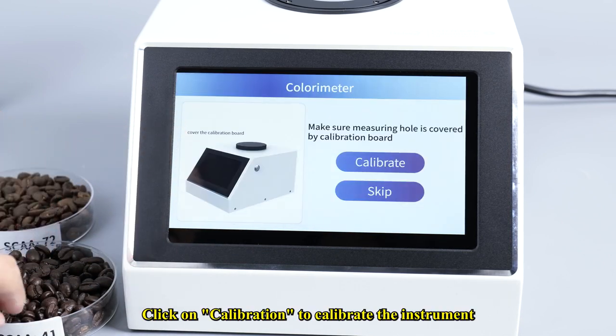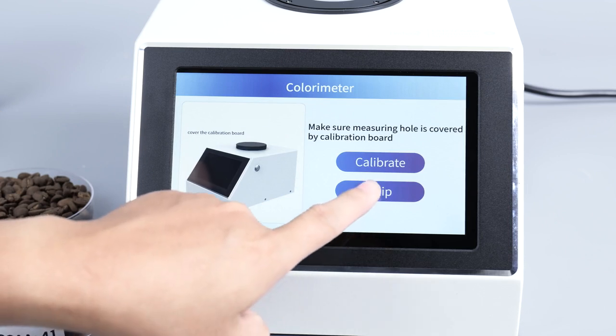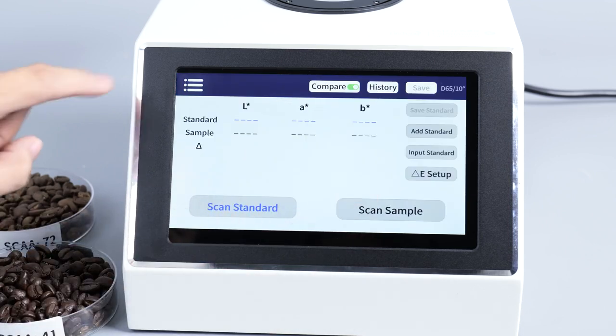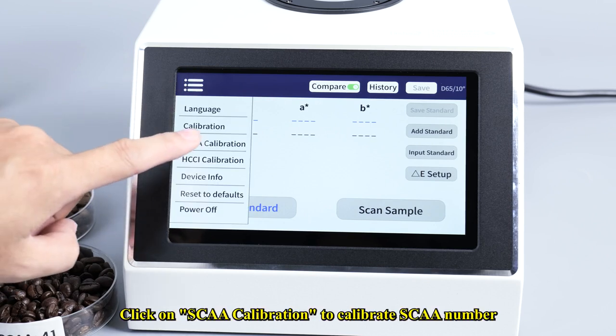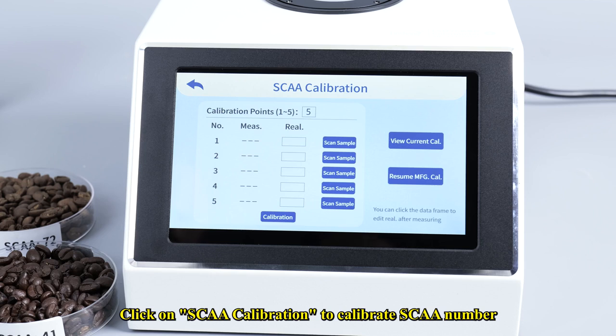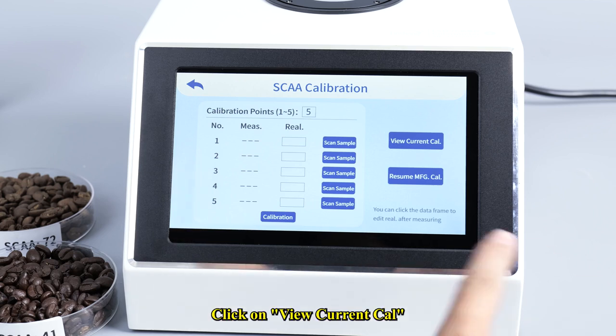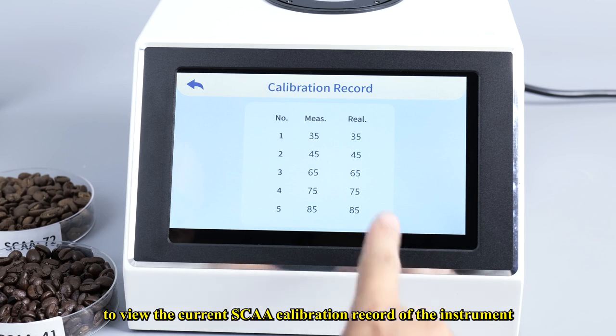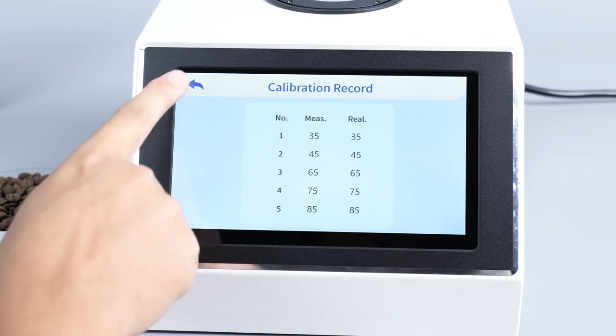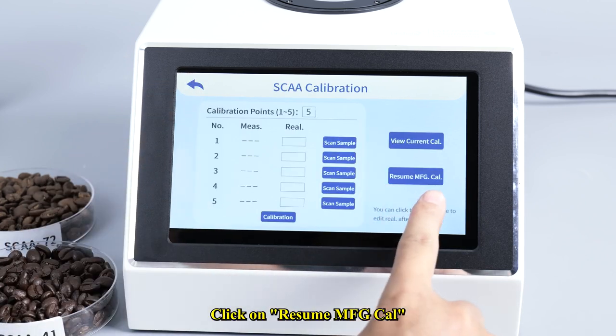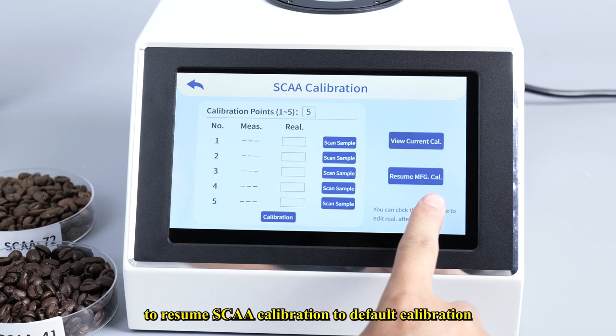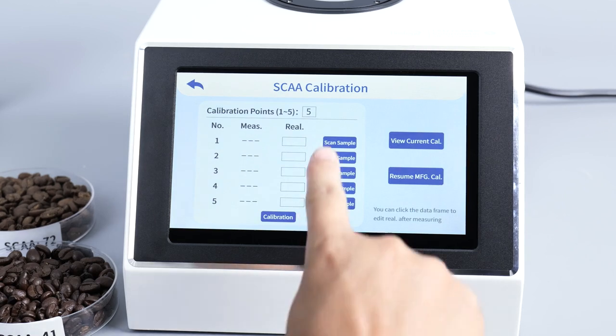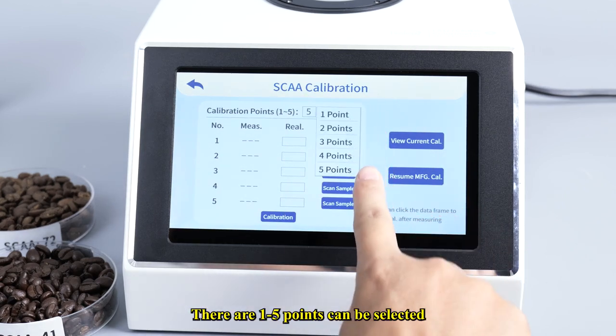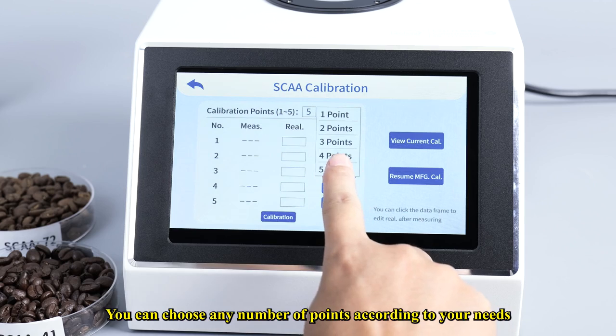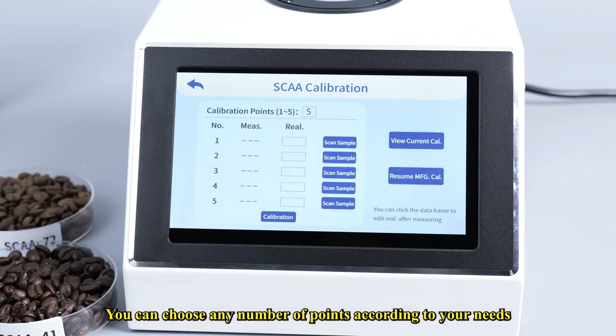Click on Calibration to calibrate the instrument. Click on SCAA Calibration to calibrate the SCAA number. Click on View Current Cal to view the current SCAA calibration record of the instrument. Click on Resume MFG Cal to resume SCAA calibration to the default calibration. There are 1 to 5 points that can be selected. You can choose any number of points according to your needs.